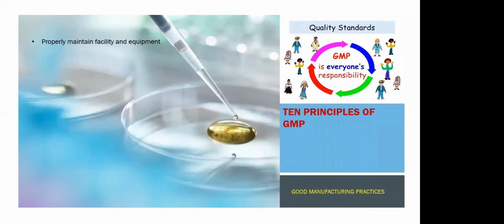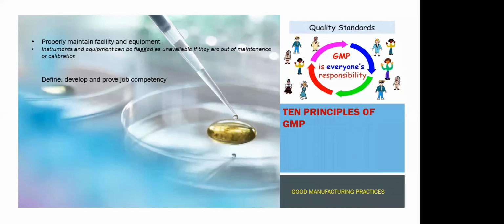Next is properly maintained facility and equipment. Instruments and equipment can be flagged as unavailable if they are out of maintenance or calibration. So it is very important that if we find some equipment is out of calibration, we immediately tag it as out of maintenance, out of use, or whatever necessary way of addressing the issue is with the particular industry. They have to put that tag on the instrument or the equipment that this is out of service, so that you may not accidentally get into that and start using it and then produce a bad product, or produce inaccurate results.